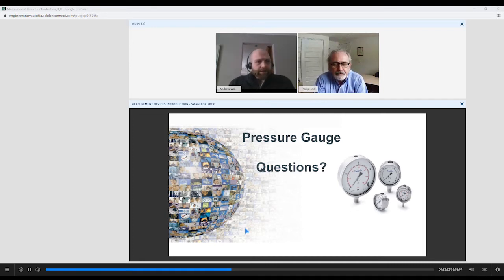Okay. Second question. This is from Michael Dentino, who would typically calibrate a gauge? Is that something Swagelok would do, or is this something a tradesperson could do? So when you buy fresh gauges brand new out of the box, you can buy them with calibration or without calibration, and that's something that Swagelok can offer should it be required. So when you go through the catalogs, there are options to include pressure gauges, and with those pressure gauges you can get a calibration certificate. Those certificates generally last about 1 year. And generally for pressure gauges, you would want to get them recalibrated every year should calibration be required.